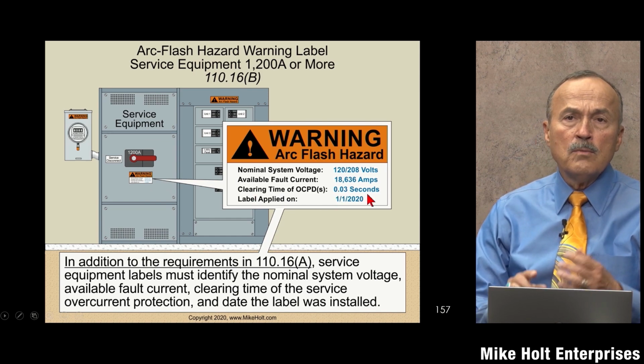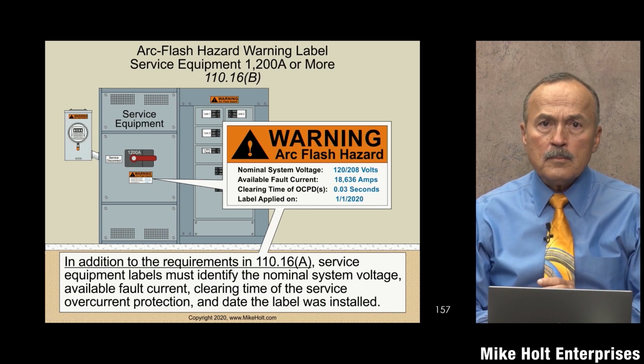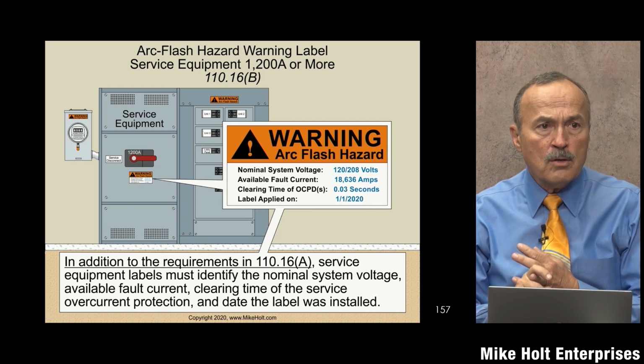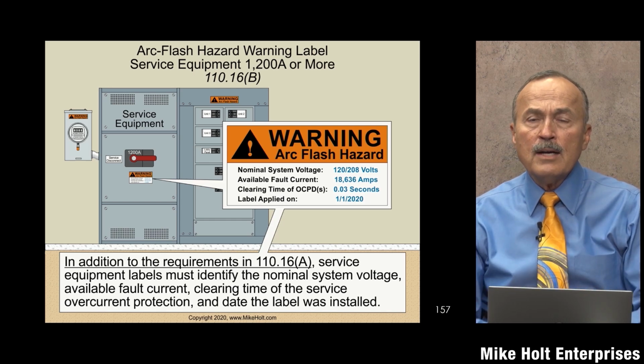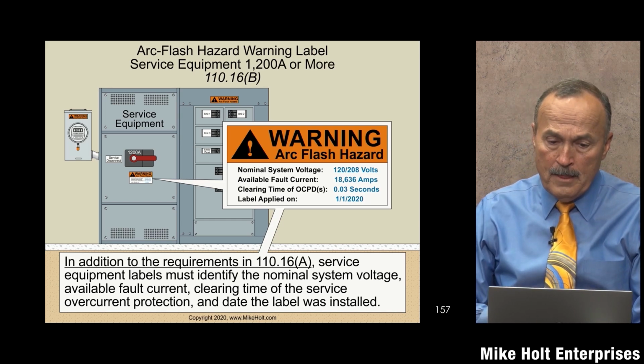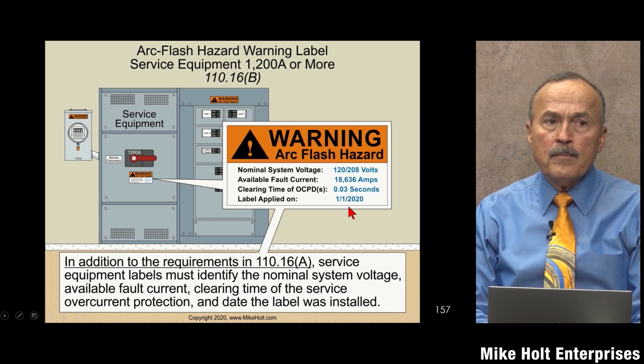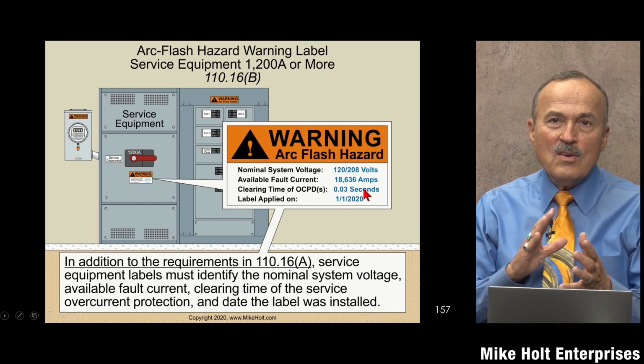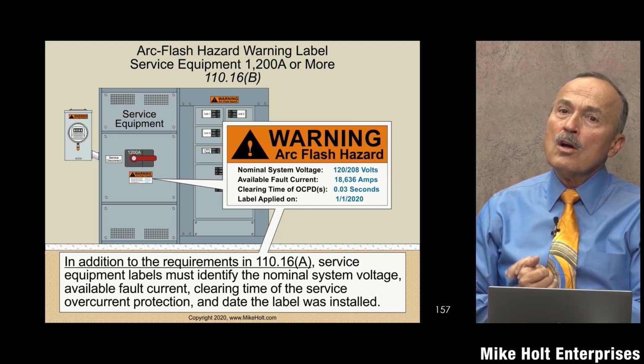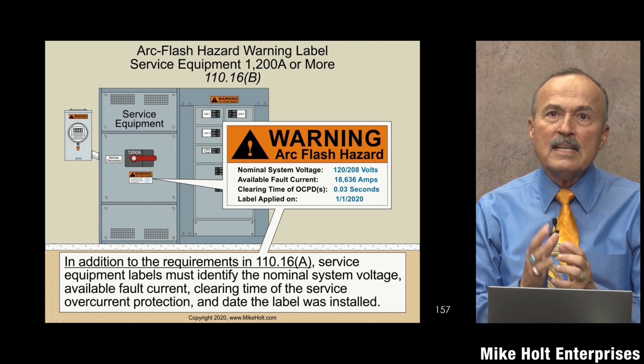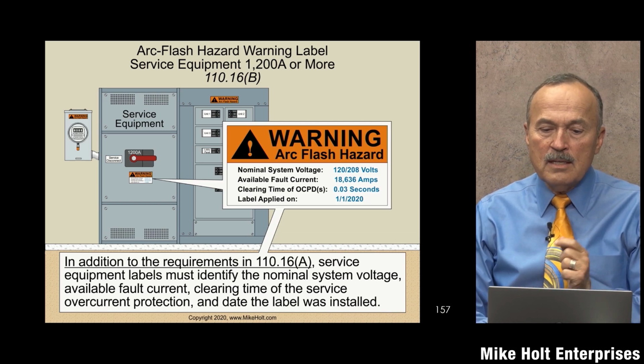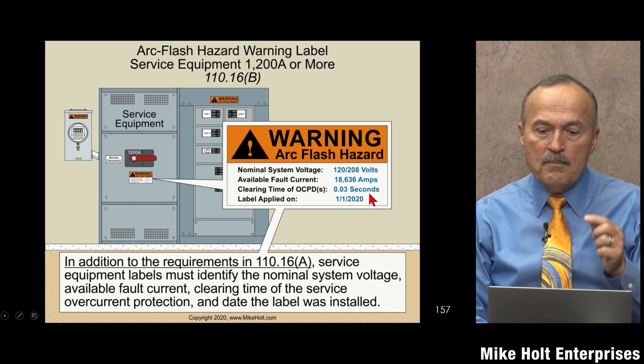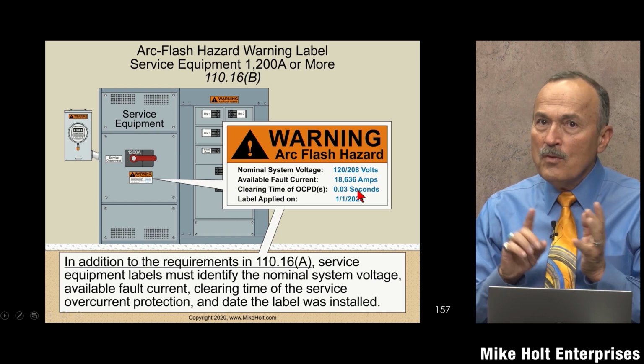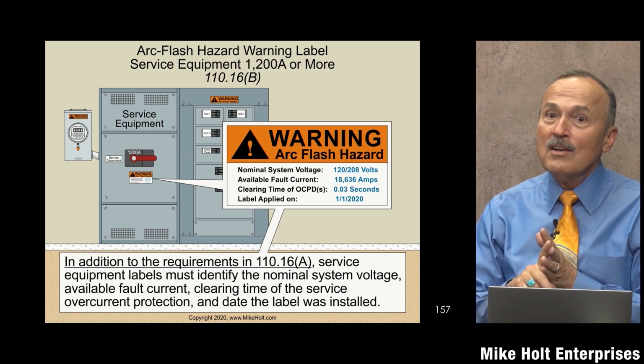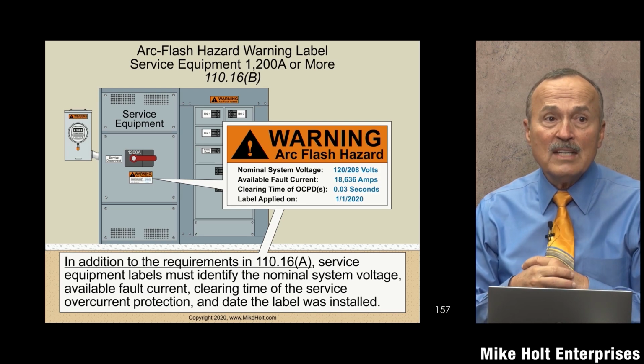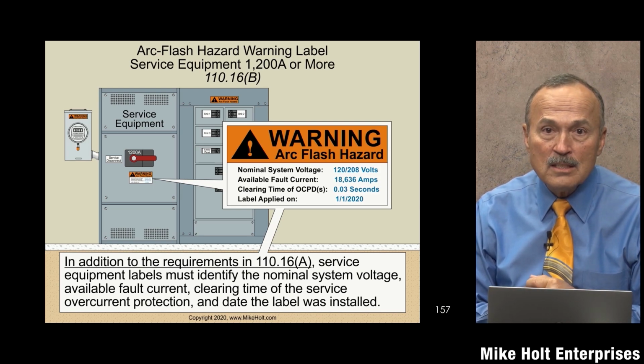That's standard. It all depends on whether it's a molded case circuit breaker, a power circuit breaker, or an electronic circuit breaker. So you'll have to get with the manufacturer of that breaker to find out the clearing time, and then the date the label is applied. So what they've done is the code can't require you to have an arc flash label in accordance with 70E, but it can require you to give the voltage, the amperage, and the clearing time. And if you know the voltage and the amperage and the clearing time, guess what? You can calculate what's called the incident energy in calories.